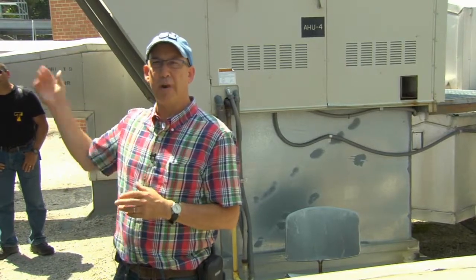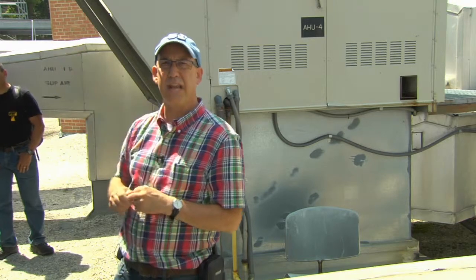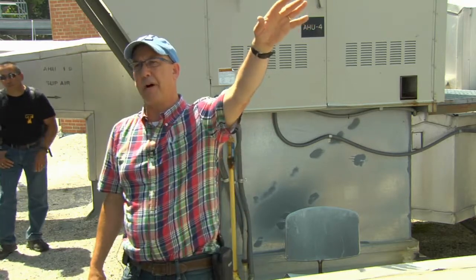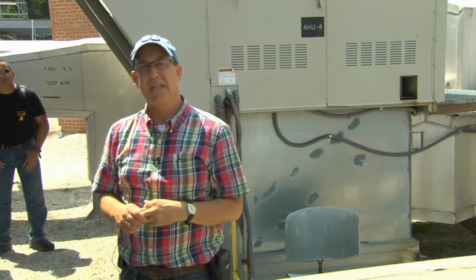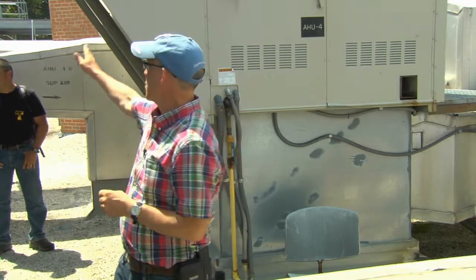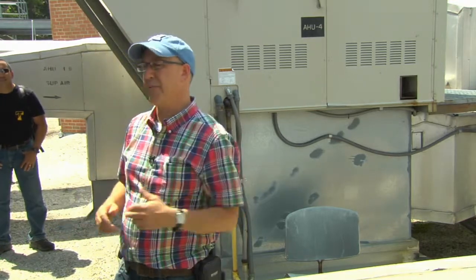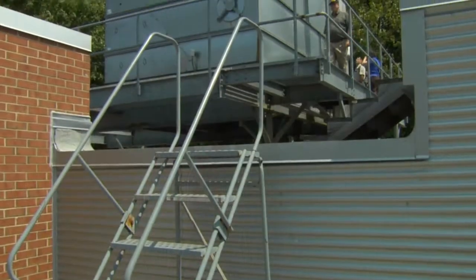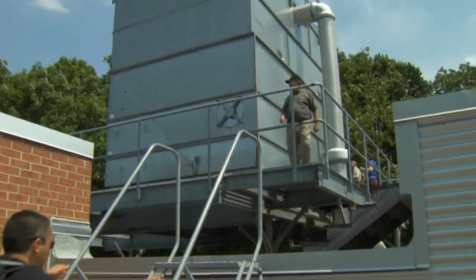The only thing I'll say on the rooftop units, most of you have already heard it, is there's some belt noise, some bearing noise on some of these units. You can hear it on the condenser fans behind me. There's a fan up above us that's got a belt noise. And the outdoor coils, again, this one's starting to get dirty, nothing bad. The next location on the walk down is the cooling towers.